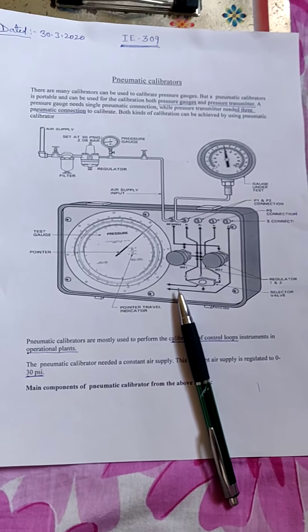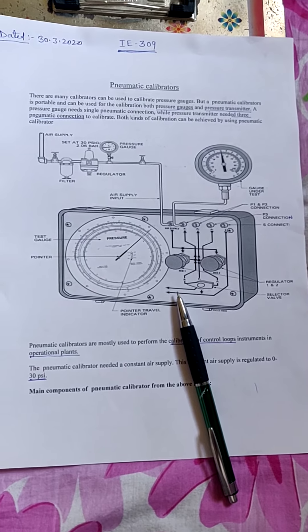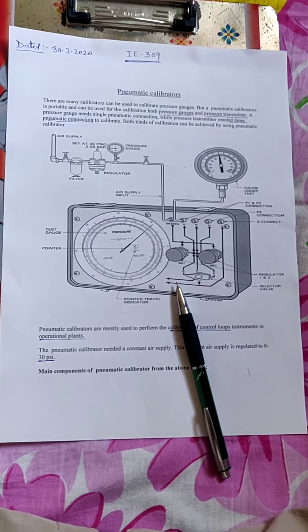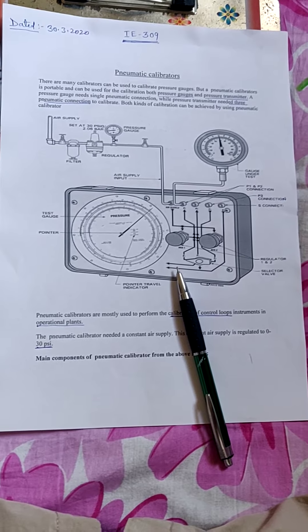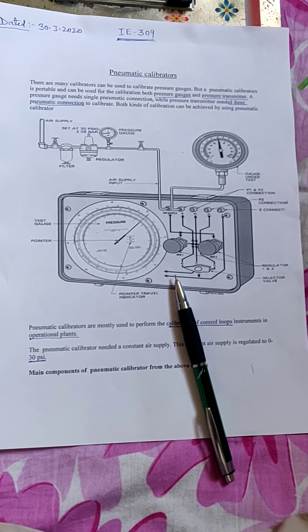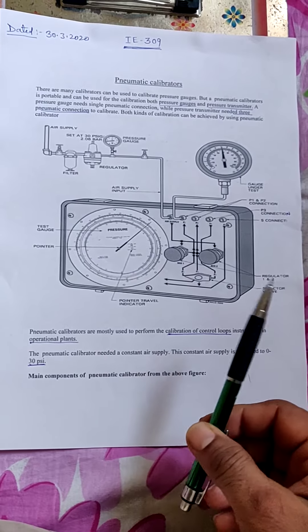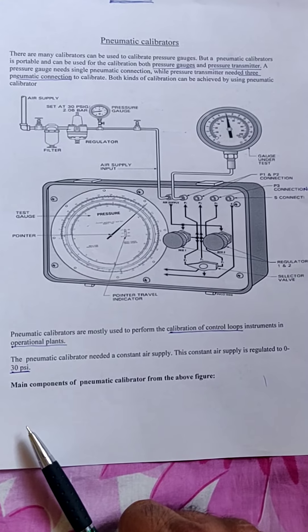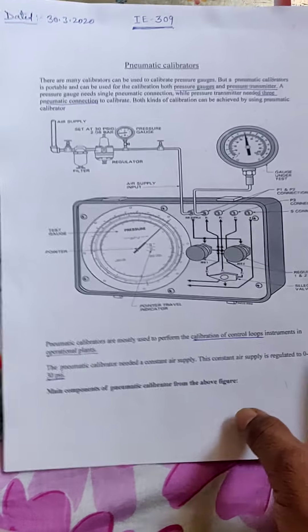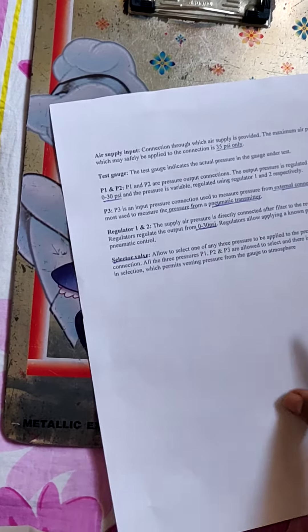In terms of percentage, first we check at zero rating, then 25% of the pressure gauge rating, then 50%, then 75%, and then 100% of the pressure rating. Then in the reverse process, we reduce it from 100% to 75%, then 50%, 25%, and then 0%. If there is some error, we make adjustments such as tightening of the spring and adjustment of the needle, so that the pressure gauge can be directly calibrated.